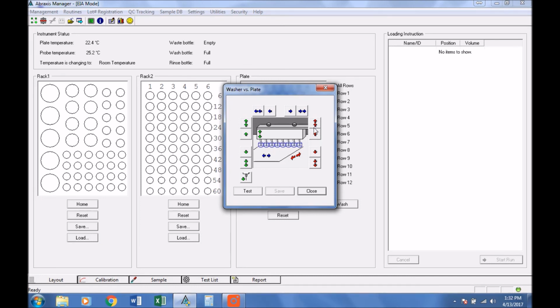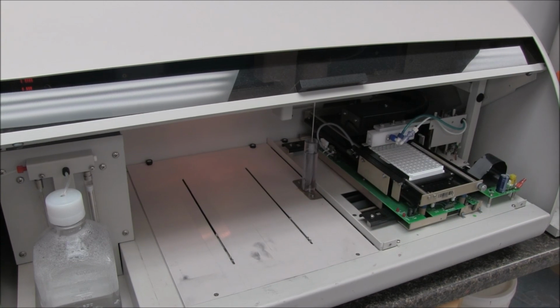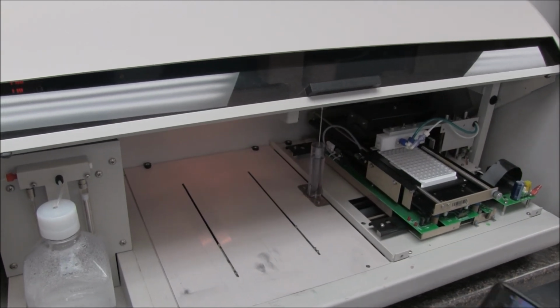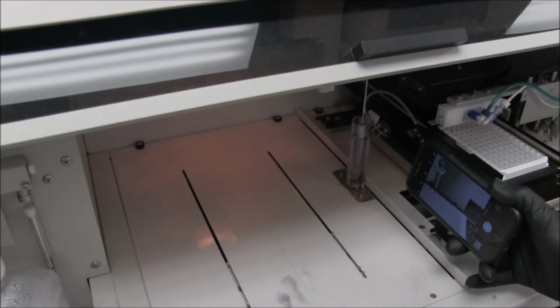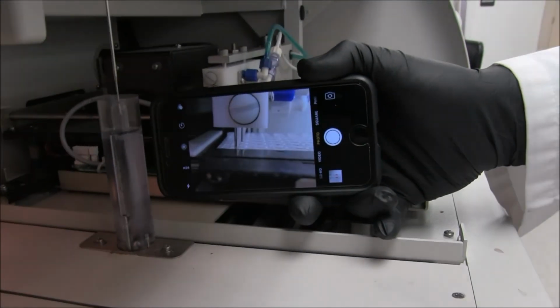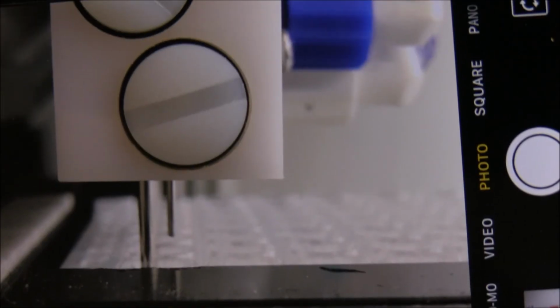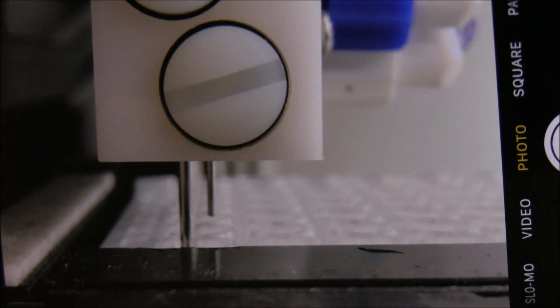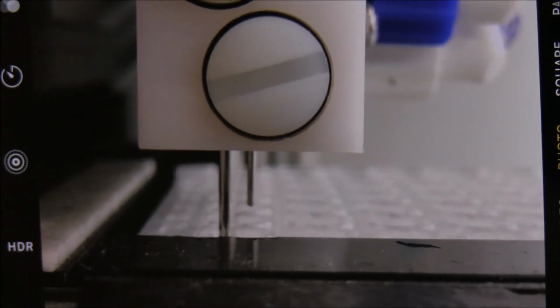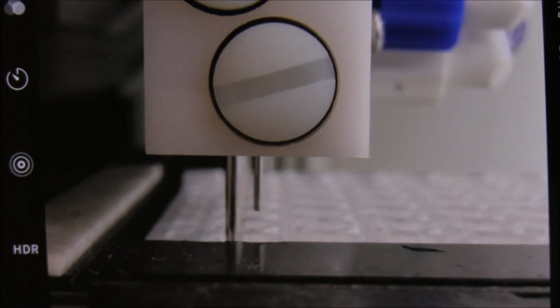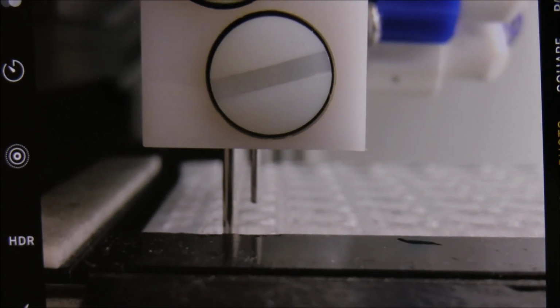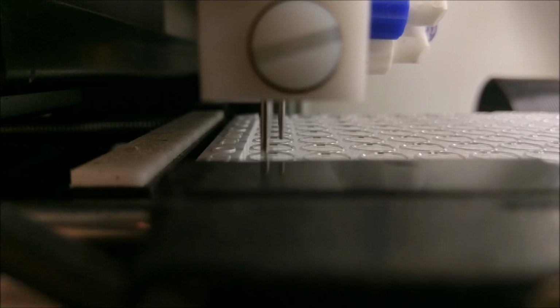In order to adjust the wash head alignment from front to back, the red arrows will be used. Utilizing a smartphone camera is an easy and safe way to complete this adjustment. The ideal positioning is when the space between both the aspiration probes and the dispensing probes is centered. Another way of describing this would be to make sure the two probe types are equidistant from the front and back of the well.